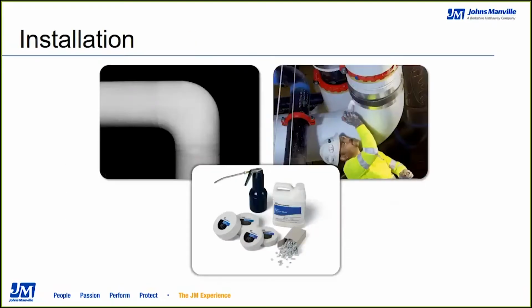Installation: if the fitting is just being used with a paper facing like ASJ, then the fitting is put on, such as the elbow you see there, and can be tacked together with stainless steel tacks. If it is a completely jacketed system, it will be installed and fully sealed with glue and mastic, as you see the contractor putting the mastic there on the right. JM does offer the full line of accessories for sealing and installing the PVC fittings as well.